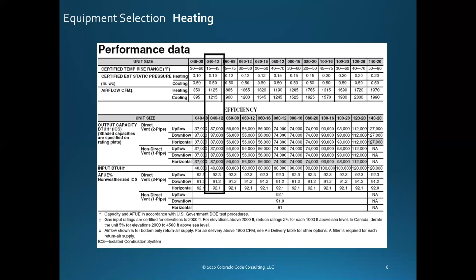And this is another thing to be very aware of when you get into very high CFM: bottom returns. With high CFMs, the squirrel cage fans love to see the air from the bottom, not the side. This is where you see, 9 times out of 10, they're taking it off the side of the return plenum on the furnace, or cutting a hole in the side. I'd love to see them up on a box while I'm sitting on a box. That return air sometimes has both the bottom and the side. The bottom's the best if you can get it. They really, really like that. So anyway, that's a pretty typical performance data piece.